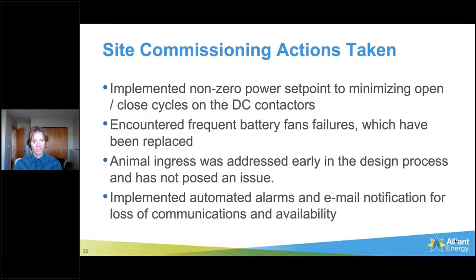Also, related to the DC contactors, we've seen issues with automated alarms not being caught by our monitoring company immediately. Part of the issue is that if the battery is in standby operation, the equipment is essentially not in service because the contactors aren't closed. By having a non-zero power set point, we're able to monitor the system availability on a continual basis.